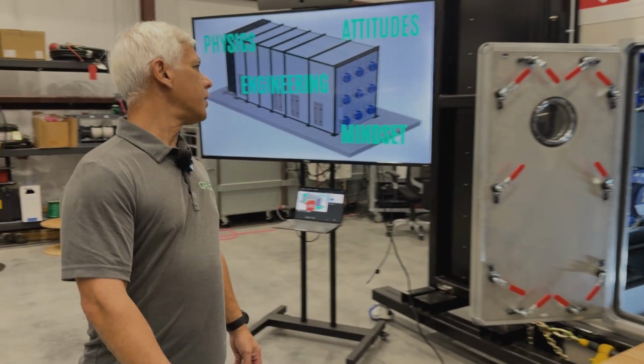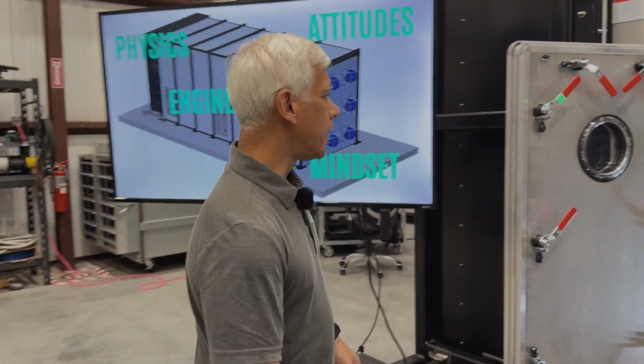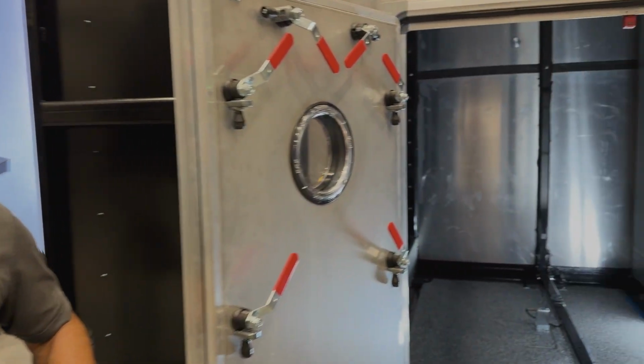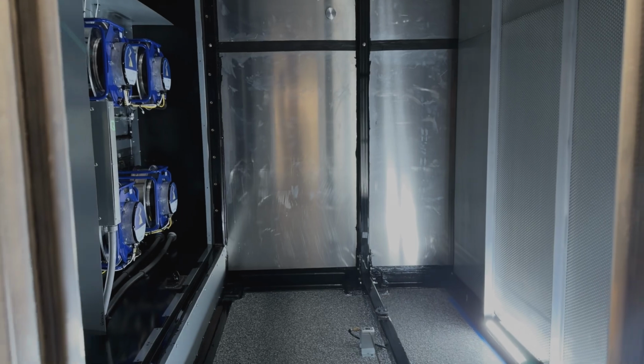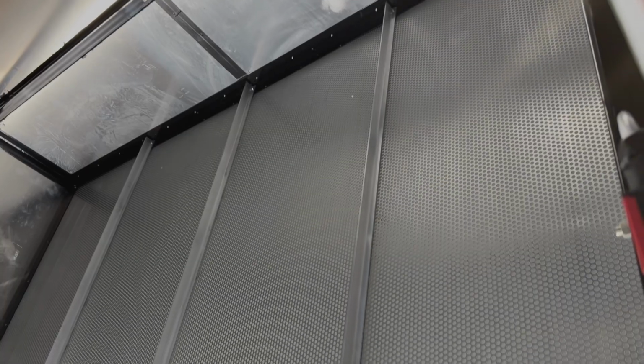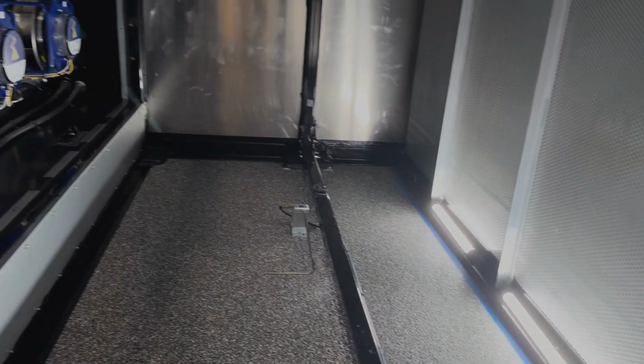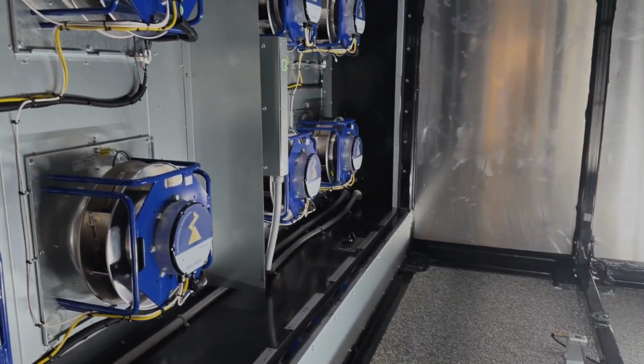All right, we are into the last section. We talked about some flow straighteners going into the test fan. Also on the right here, we have flow straighteners going into the nozzle section. That's because we need to make sure every nozzle sees the same airflow, because we measure pressure difference across the whole section. If the different nozzles are seeing different pressures, then that's going to throw our number off. So we need to get clean airflow into each of those nozzles.